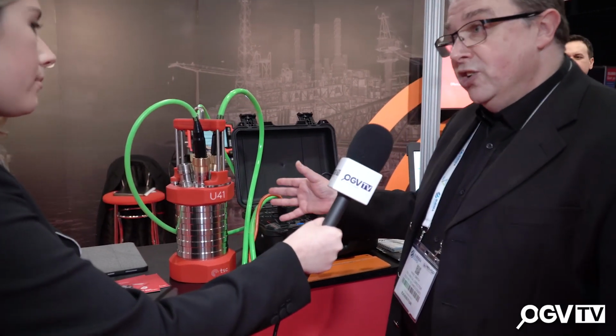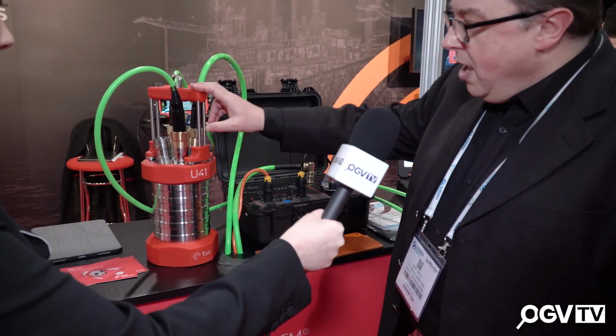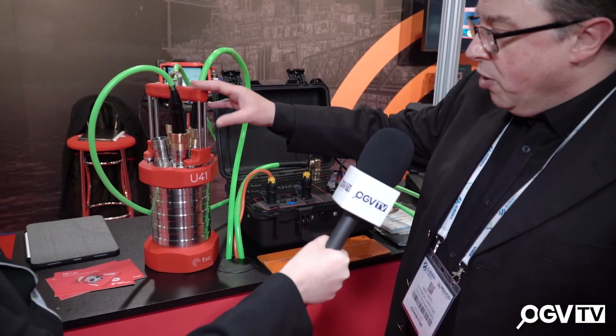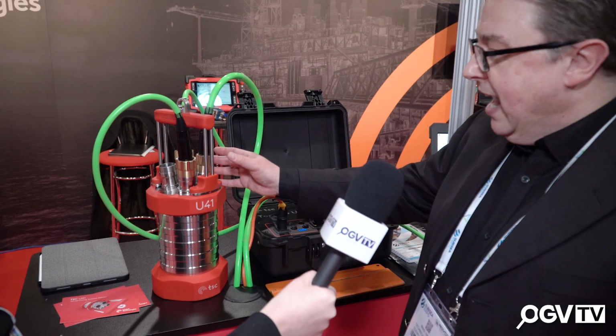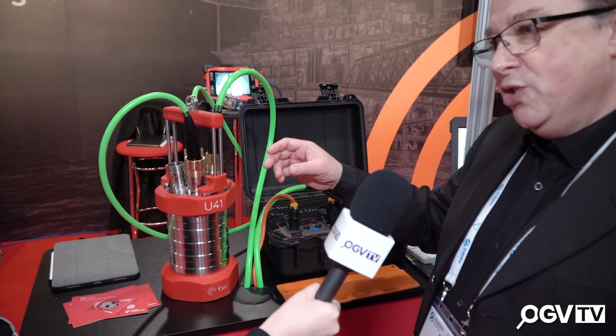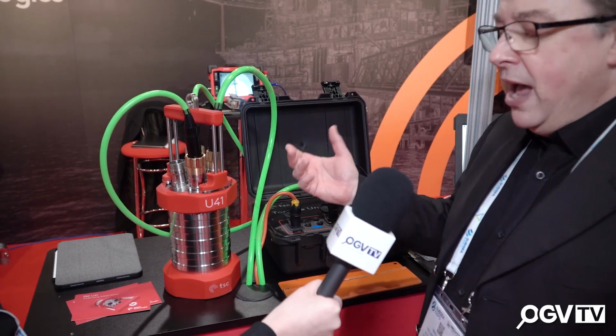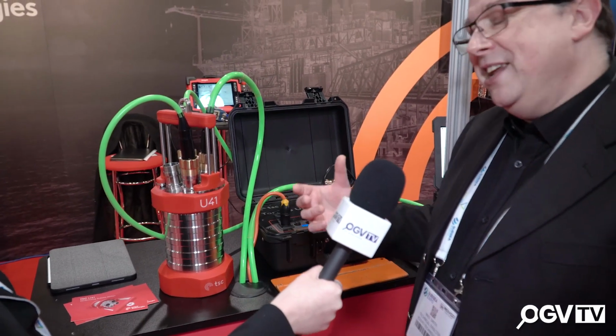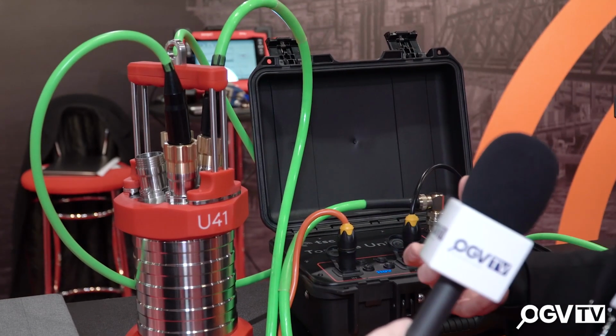So let me tell you a little bit about the instrument that we've got here. This embodiment is for diver deployment. The diver would take this subsea bottle down with them, and attached to the bottle are up to 3 individual ACFM probes. This is a big improvement over the previous generation, where we could only attach 1 probe at a time. If the diver came to a different geometry, perhaps, where they needed to change probes, we'd have to recover the unit to the surface, change the probe out and put it back down again. That all takes time and cost. So we've added these 3 probe connectors so that a diver can very quickly switch between different probes and utilise their time more effectively.